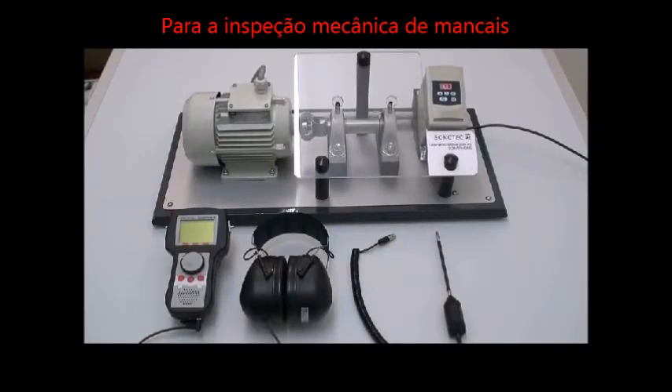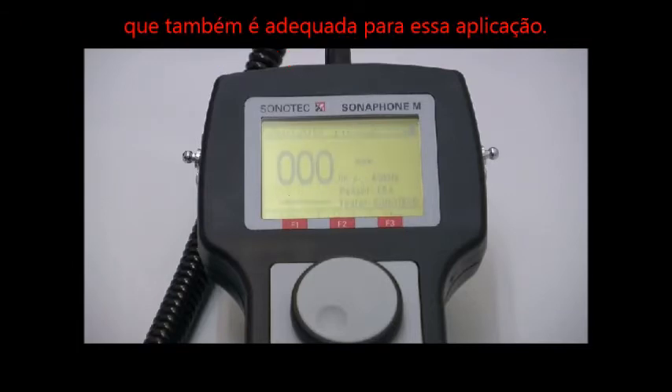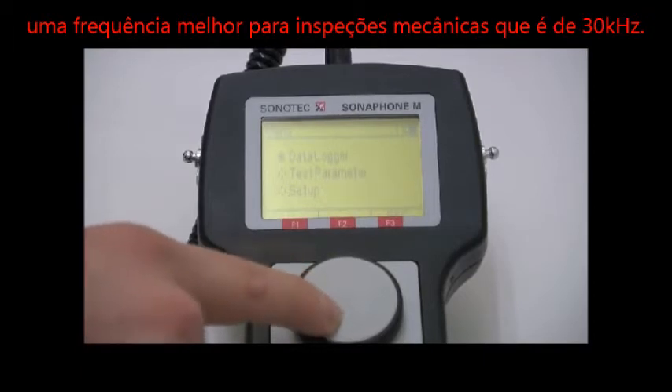For the mechanical inspection of bearings, we are using the Sonaphone in combination with the airborne contact probe L52. The Sonaphone models R, RD, and K operate with a preset frequency of 40 kHz, which is also suited for this application. However, models M and E can be tuned manually to the optimal frequency for mechanical inspections: 30 kHz.